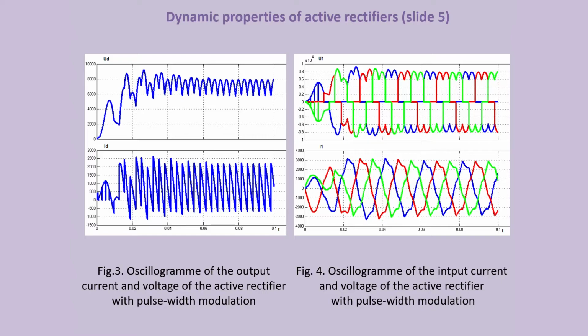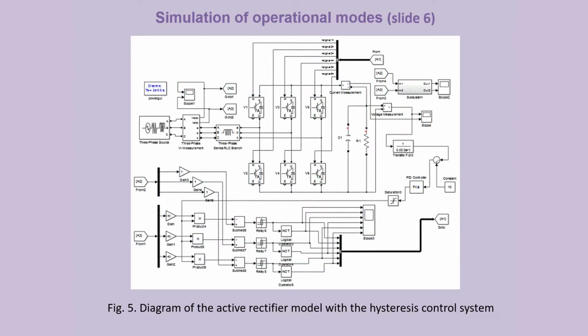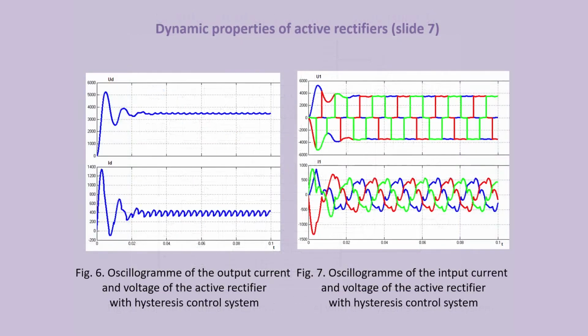1.0. The form of the current curve is determined by the two-level active rectifier and the ratio of active and inductive resistance of the power transformer of the mine substation. The time for the output voltage to increase to the set value makes 0.02 sec. The pulse number m is equal to 6. Figure 5 shows the diagram of the active rectifier model with the hysteresis control system. Figure 6 contains the oscillogram of the output current and voltage of the active rectifier, while figure 7 presents oscillograms of the input current and voltage.